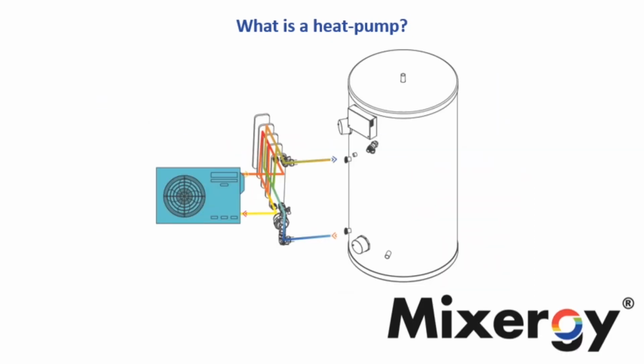So today we're going to be talking about the performance of this heat pump unit system, and when it's heating a Mixergy heat pump ready cylinder. This is really a proxy for any cylinder, but there are a number of benefits that the Mixergy system has. One is that we're able to utilize the capacity of the cylinder much more effectively with our heat transfer module that sits on the outside. That means that you can get up to a third more hot water from the same cylinder size. You can install a smaller cylinder or have a slimline version, quite a lot of flexibility. Because they're heat pump ready, of course, you can install a gas boiler today, or a tank that's just using direct electric, and retrofit with a heat pump in the future with our heat transfer module.